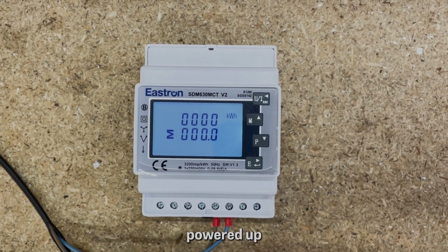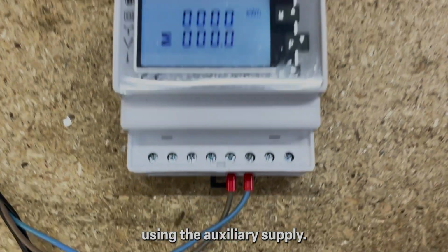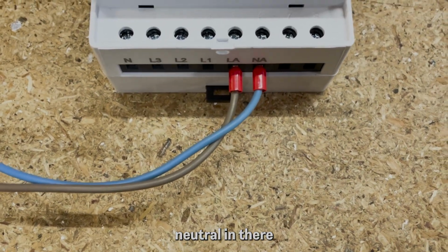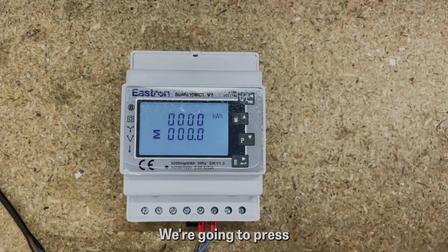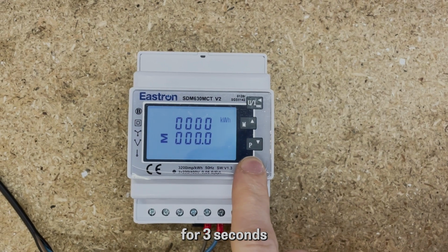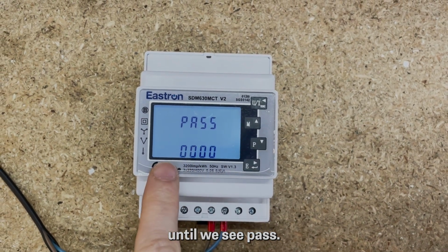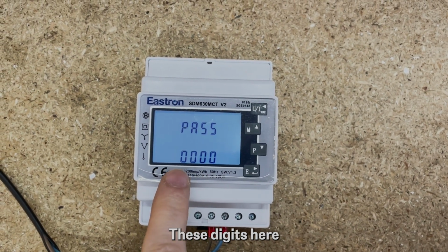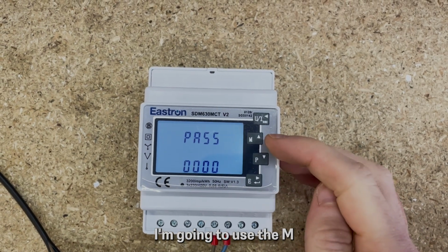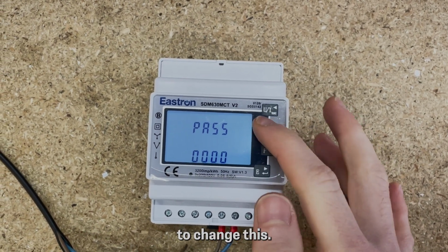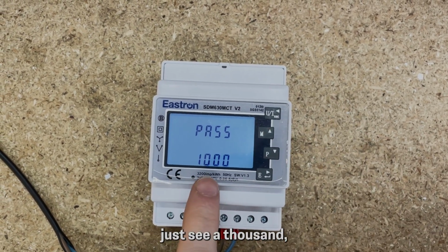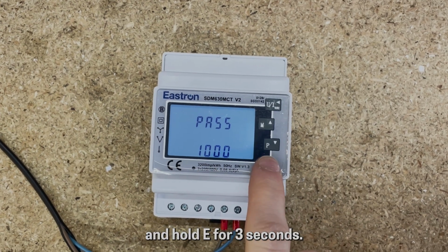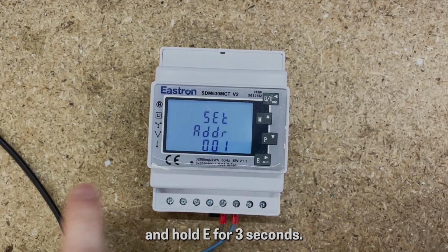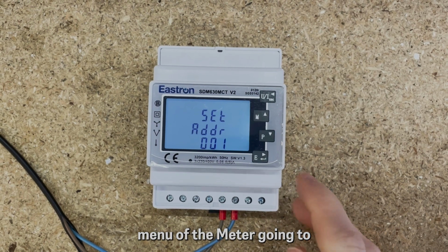So we've got the meter here powered up using the auxiliary supply, just a live and neutral in there to give us some power. We're going to press and hold the E button for 3 seconds until we see pass. And we've got these digits here with the first one flashing. We're going to use the M or the upwards arrow to change this. Just tap it once, change this to 1000. And then we're going to press and hold E for 3 seconds. And now we're in the settings menu of the meter.